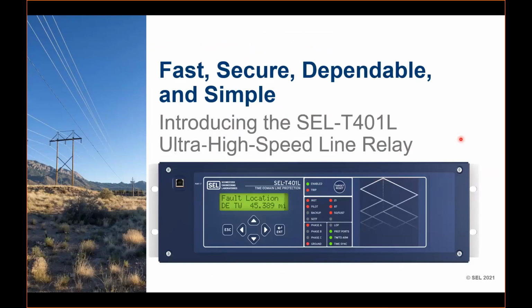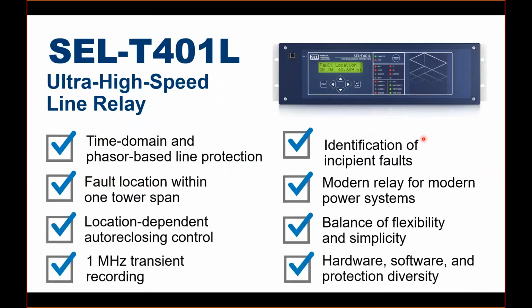It's basically a variant or an advanced version of SEL-T400L that was launched 3 or 4 years back. So this is kind of a solution which will provide you the modern technologies, traveling wave, incremental based technologies, plus the conventional phasor based technologies. So it's basically a combination, and you can use this as a standalone line protection relay for any kind of fault, for any kind of feeder.